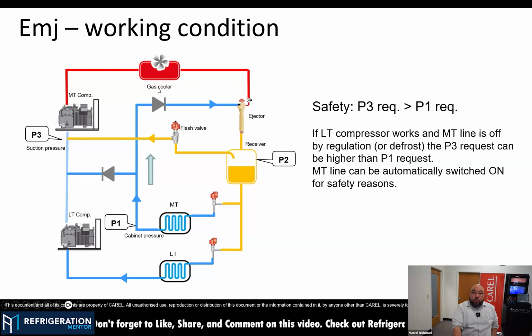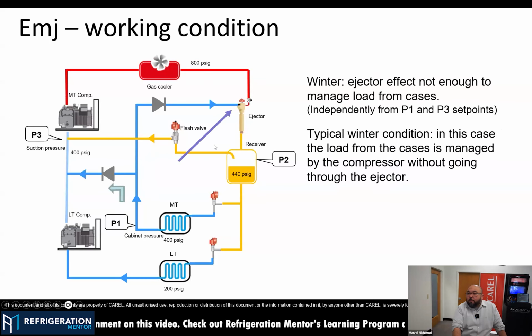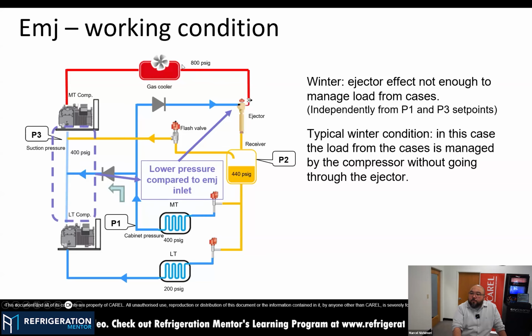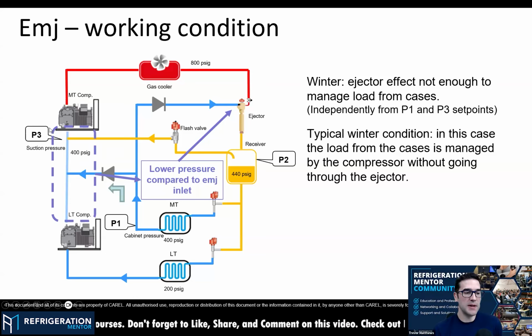Yeah, so if you have cold ambient conditions, like outside is colder and the cases are good, let me pull up the low temperature conditions here. During winter conditions, if you have a very cold night, the pressure on the gas cooler will be lower. So the energy to pull refrigerant from here will be reduced or almost zero. The ejector will be working as an HPV only, controlling the pressure. The liquid receiver will always continue maintaining the pressure here, and depending on conditions, it could be almost closed. MT line could be closed, due to the curtains, if it's night and so on. So all the LT line will be compressing here and maintaining the pressure based on this P3 probe. If I have a few cabinets on and running, flow will come in this direction. Yeah, perfect. Makes sense. I'm not sure if I answered your question, Trevor.